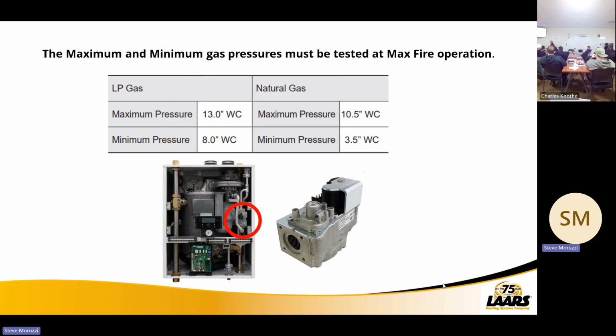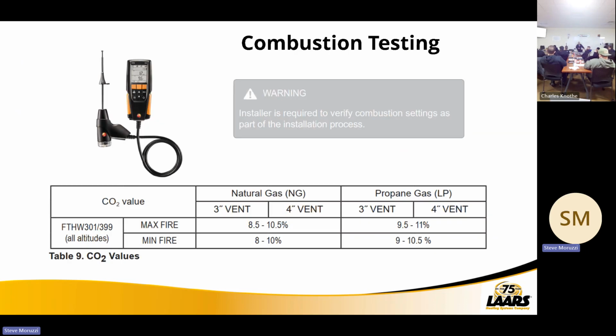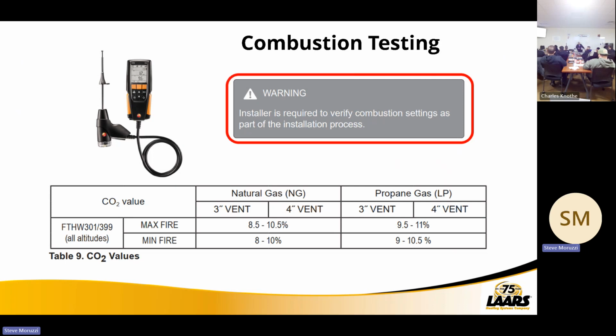Combustion setup, we've talked about the pressures. Now, also what I'm showing here is right off the top or bottom. A lot of times, guys go to the gas valves, they want to do readings, incoming gas pressure off the valve, which you can, and that's what we offer on the wall hung in smaller size, the 199 floor boiler. But with the 301 399, the gas connection off the top or the bottom would give you a test plug. And there is an O-ring gasket there, so don't drop it or lose it, guys. Be cautious of that. And you can measure your incoming gas pressure right there, as well as don't forget, we don't want to see greater than a 1 inch pressure drop, inches of water column. So it's required on all installations.